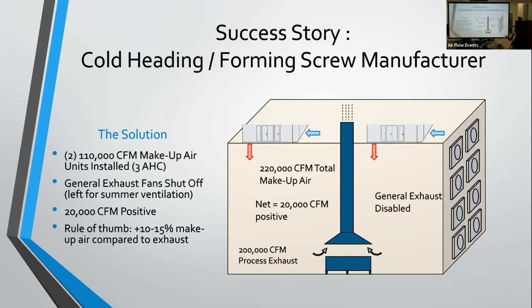Typically, we ended up with 200,000 CFM of process exhaust and 210,000 CFM of makeup air. As a rule of thumb, you'll see anywhere between, this says 10, I think it's actually more like 5 to 15% additional makeup air compared to your exhaust air is a good rule of thumb to follow.